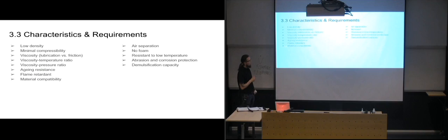And we want material compatibility, because when we are creating systems, the seals that we are using are often rubber solutions, but they can be a lot of other things. They can be quite hard fiber solutions that we are using to seal our openings, and some of them react negatively when they come into contact with especially mineral oil. So if we are using seals in our system that will react negatively to mineral oil, we will have to go for synthetic oils, which are more expensive. So that is something we need to look at when we are creating the system, that we won't have any clashes of compatibility there. So if you're putting in the oil you think is the best for the system, but you don't remember that one of the seals is going to be destroyed within a year if it's in contact with this oil, then it's not that good for the system.